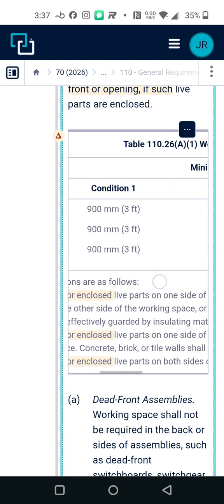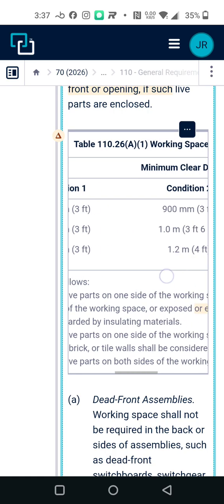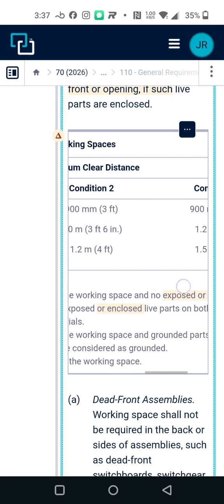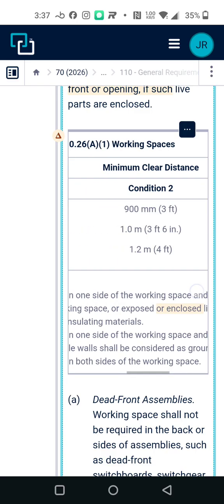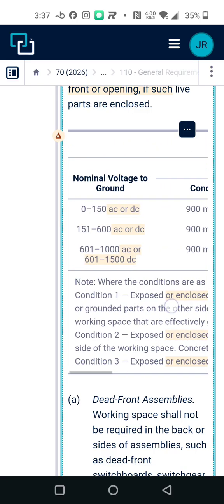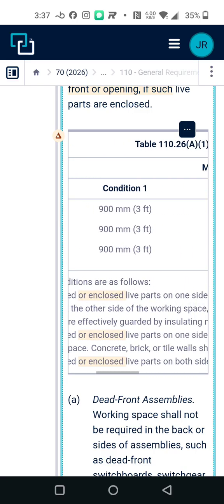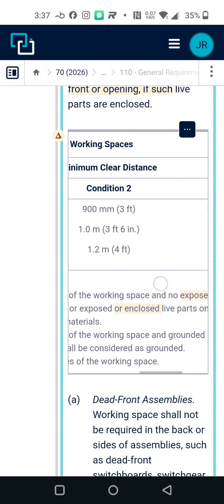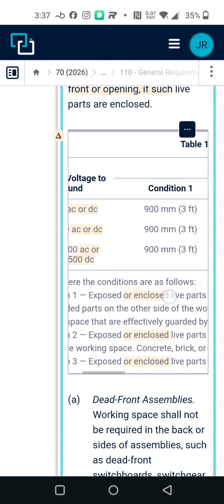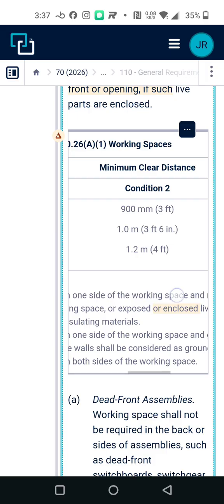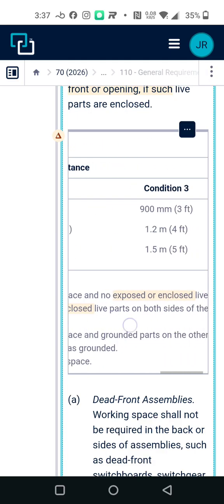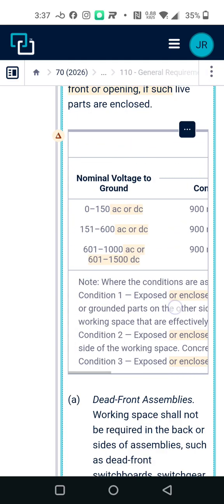Expose or enclose live parts on one side of the working space and grounded parts on the other side of the working space. Concrete, brick, or tile walls shall be considered as grounded, and expose or enclose live parts on both sides of the working space. And you have different conditions, stuff like that.